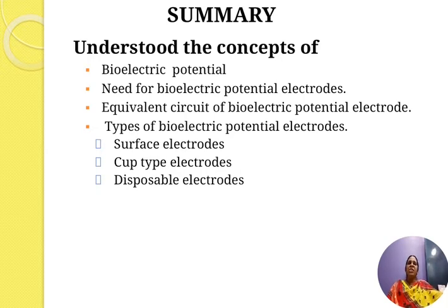Then we have flexible body surface electrodes, which are formed by depositing a metal film, for example silver and silver chloride, on a flexible substrate. Usually the substrate side receives a layer of conductive adhesive to fix the electrode to the skin. These are very thin, flexible, easy to adjust to the body contour and stay in place for longer periods.